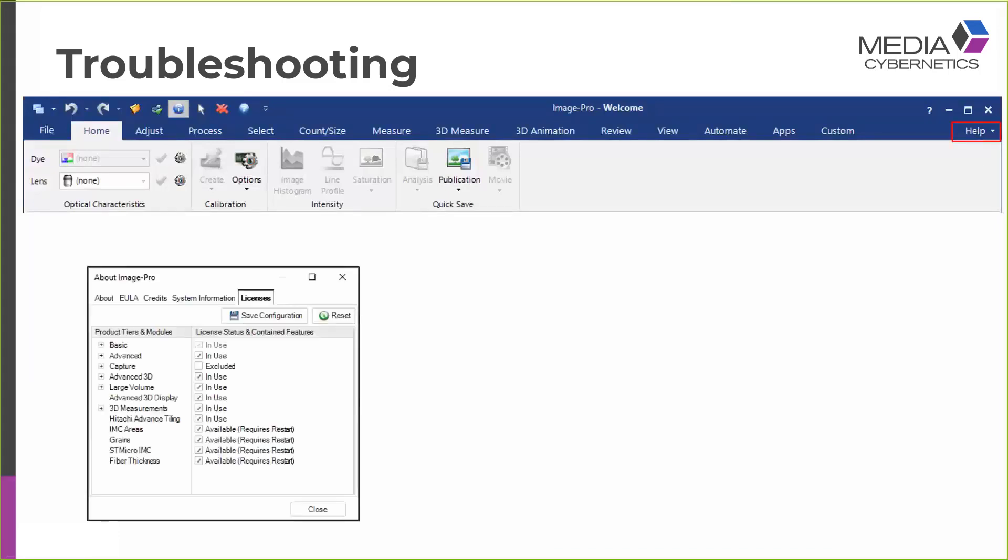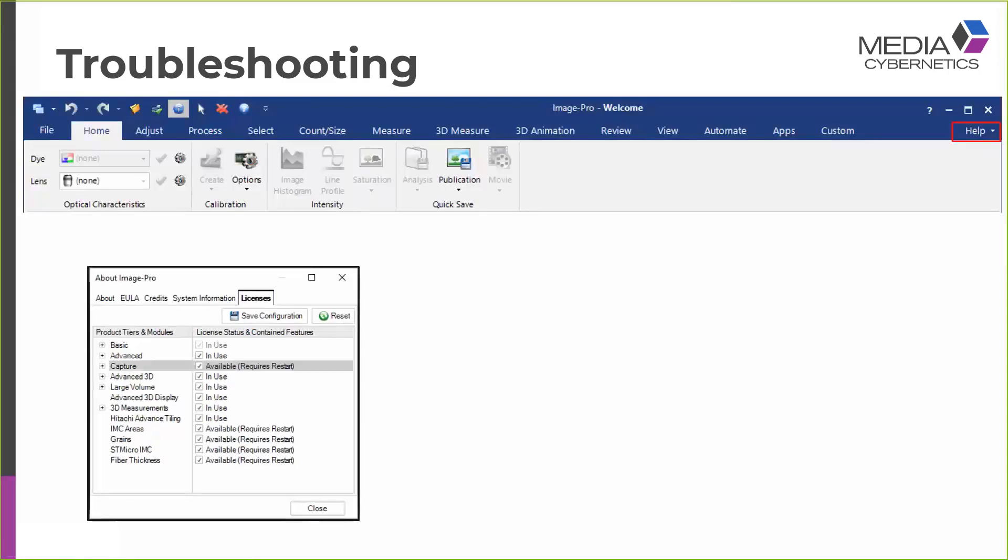Another problem you may encounter is that when you load Image Pro, you may find that instead of having a Capture tab, you see a Home tab. This is indicative of there not being a Capture module loaded. The way to check this is if you go to the Help menu on the right-hand side of the application and you open the About Image Pro dialog and then select the Licenses tab, you can check to see whether the Capture module is included or has been disabled. Here I see the word excluded, so a user has disabled the Capture module. The solution is, of course, just to check the box and make the module available.